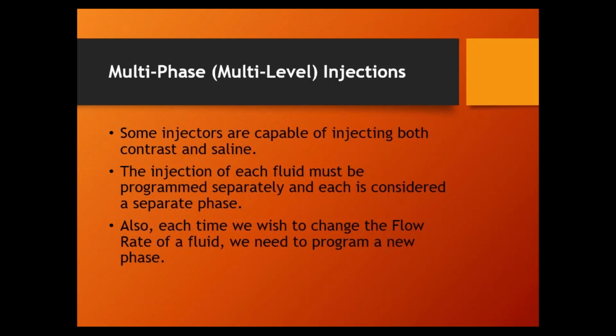That's a 4-phase injection. Now, I just picked random numbers to demonstrate that. The reason you would want to do that, again, if this is an angio injector, so it just has the one syringe, there's no saline syringe. The only reason you would program a multi-phase or multi-level injection on an angio injector is to change the speed of the injection in the middle of the injection. Most of the time, they just change it once. Most of them are just two-phase injections, but they can go up to 3 phases, 4 phases. The Spectris Solaris, Medrad's MRI injector, I think goes up to 6 phases. I don't know if I use that, but it's capable of it.